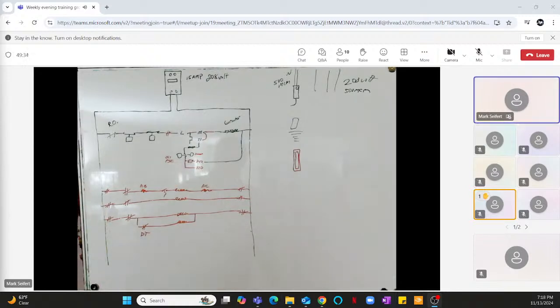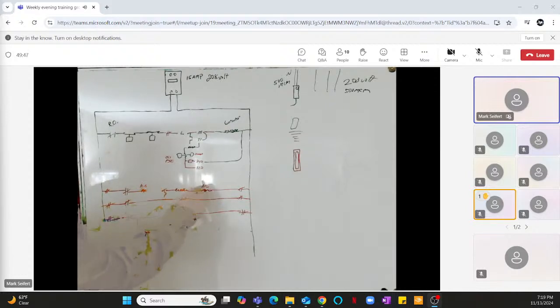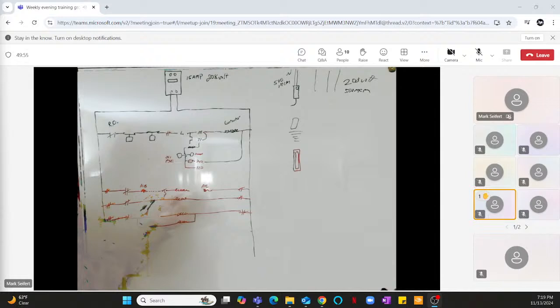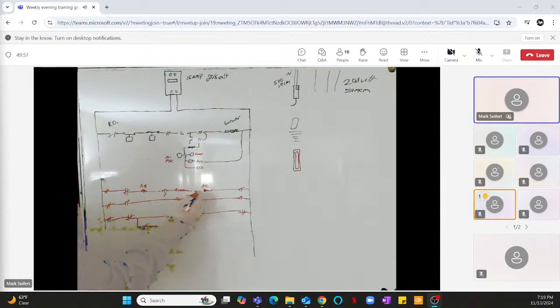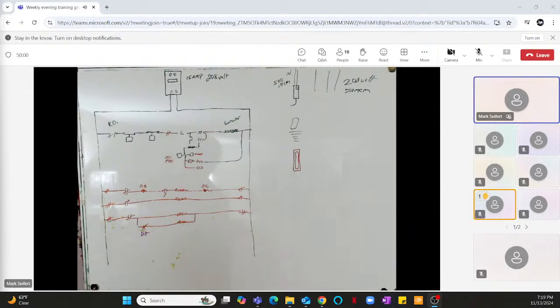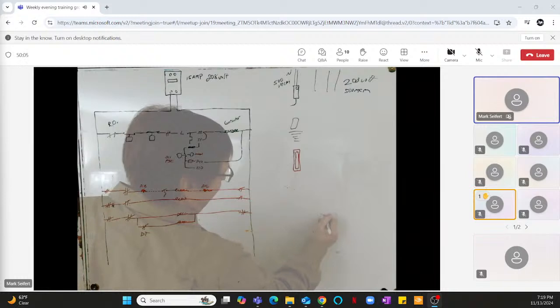These wiring diagrams could be on the rack most of the time. What you're going to find, these are almost always custom made. Let's just say this is out of the case. You're going to see right here will be a dotted line. That dotted line means field installed. How do I know that? Because every time you look at the corner of the wiring diagram, it's going to show dotted line. It's going to say field installed.